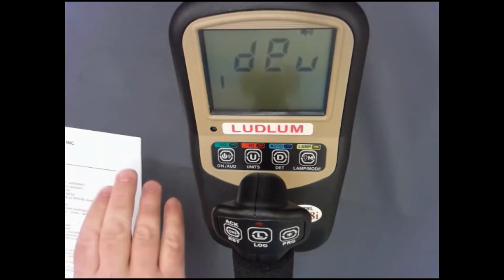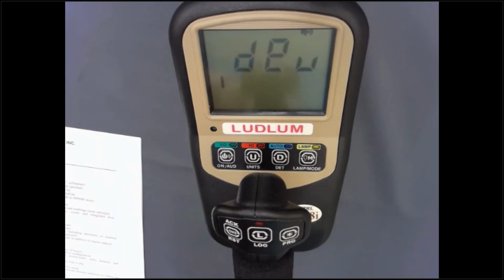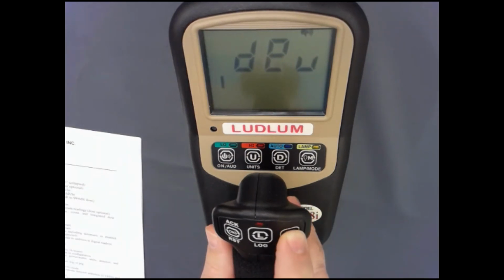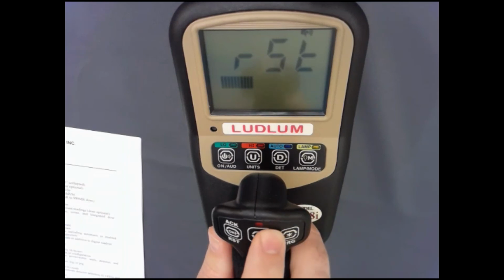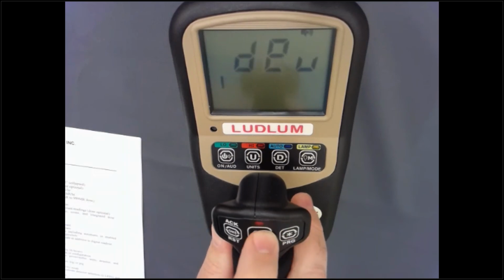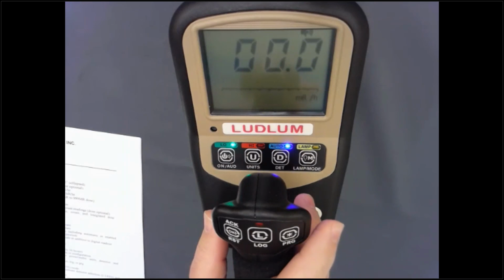And in this case, we get into a setup menu, and there are a number of different screens, and the manual will have detailed information as to how to navigate through these screens and do the settings. But in this particular case, we're just looking at the device menu, the log menu, a configuration menu, calibration menu, channel 1 menu, unit 1 menu, and unit 2 menu, and a reset feature, which is used by us here at our plant to reset the instrument back to defaults, and can be used in the field in critical applications, but it's password protected. So if you need to use that, please give us a call. And then pressing and holding the log button will take us back to our main screen.